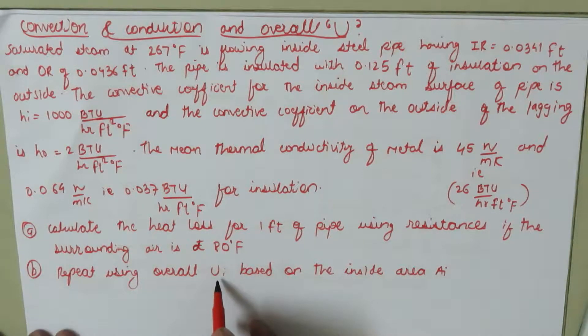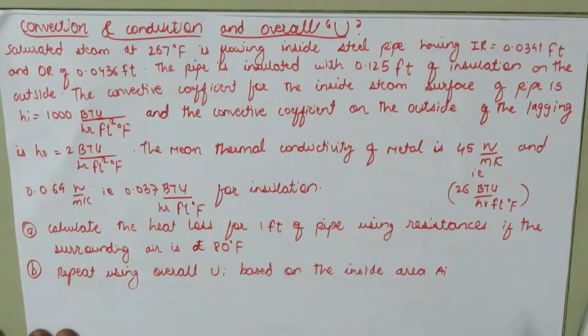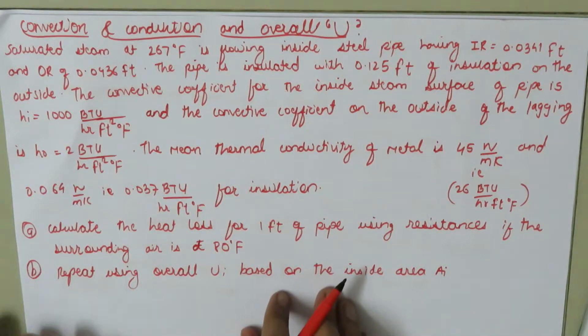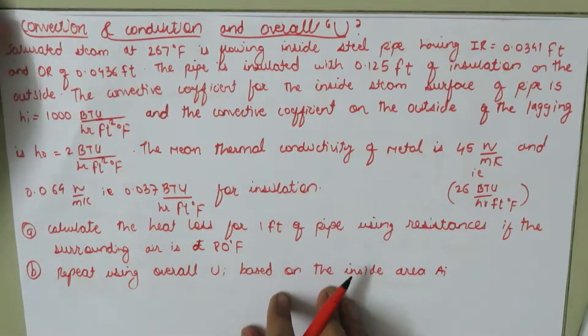The convective coefficient for the inside steam surface of the pipe is 1000 BTU/hr·ft²·°F, and the convective coefficient on the outer side of the insulation is 2 BTU/hr·ft²·°F. The mean thermal conductivity of the metal is 26 BTU/hr·ft·°F and for the insulation it is 0.037 BTU/hr·ft·°F. We are asked to calculate the heat loss for one foot of pipe using resistances, and then repeat using the overall heat transfer coefficient.